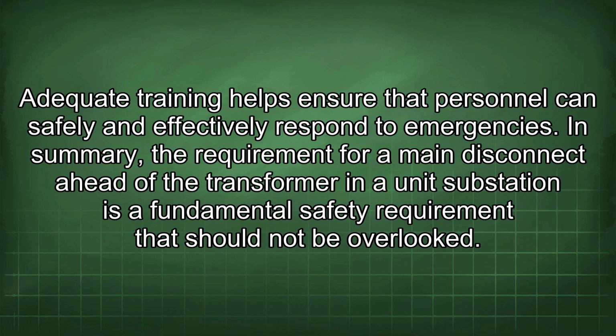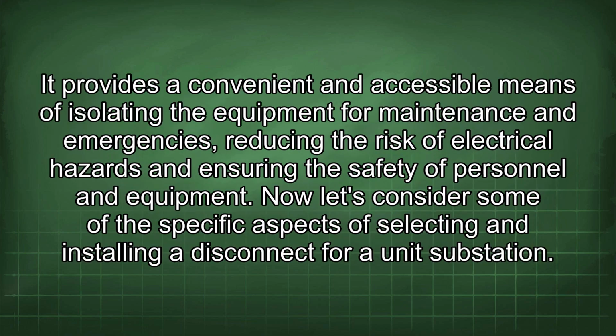In summary, the requirement for a main disconnect ahead of the transformer in the unit substation is a fundamental safety requirement that should not be overlooked. It provides a convenient and accessible means of isolating the equipment for maintenance and emergencies, reducing the risk of electrical hazards and ensuring the safety of personnel and equipment.